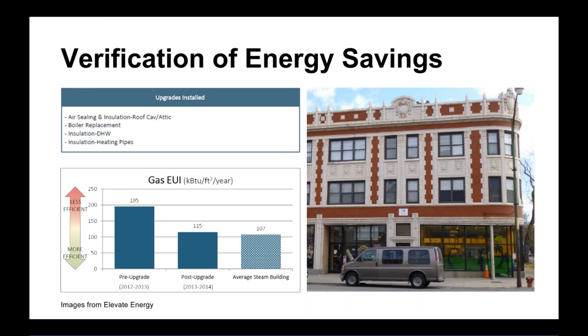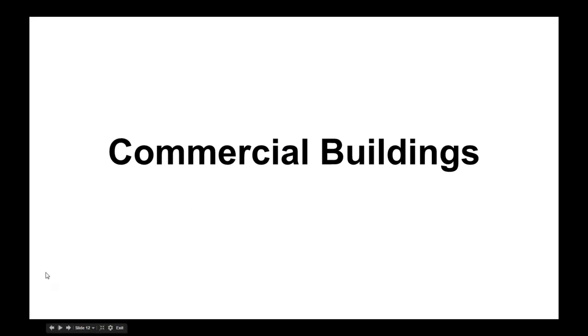You can see we included a comparison to the average steam building, and this building is still a little higher than average for steam buildings in Chicago — maybe because they still don't have great controls over their boiler or didn't do a lot of steam balancing. That shows there's still opportunity to improve efficiency further, even though it went down drastically since they received the upgrades. With that, I'm going to turn it over to Erin, who's going to talk about commercial buildings.